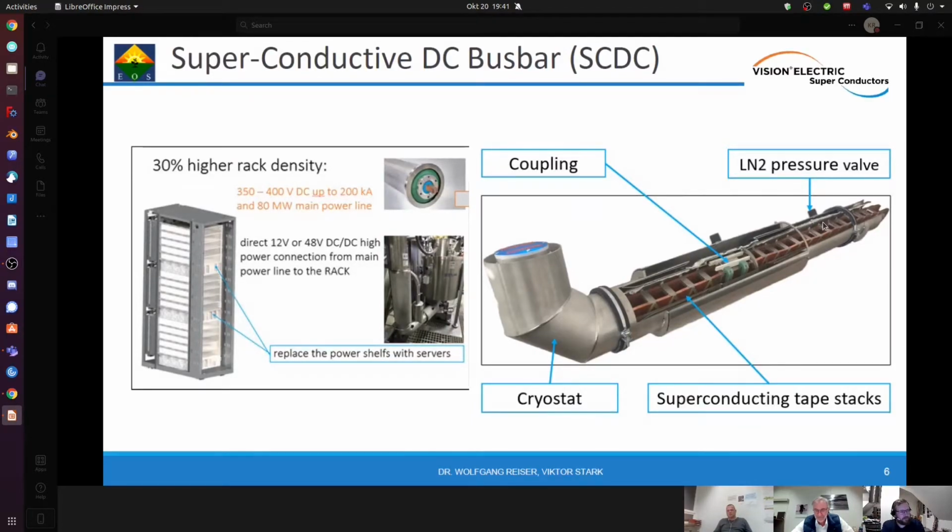You raise a very good point, because I think that was an exciting discovery, that with basically introducing liquid nitrogen to a data center, this can easily be multi-purpose, and by integrating the busbar correctly in an ideal way, you can create a more efficient and cost-effective cooling solution, and you also already have the tools for firefighting included in your electric busbar, right? So combining those components, this is really an exciting new way to think about data centers.